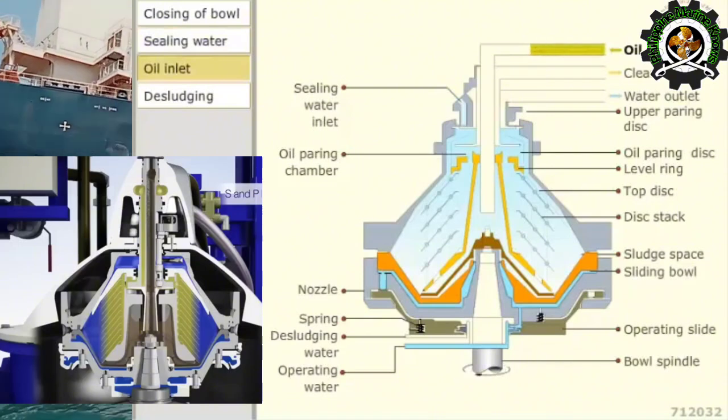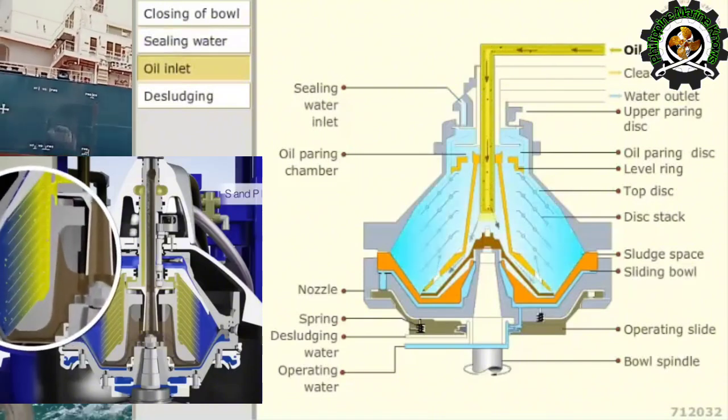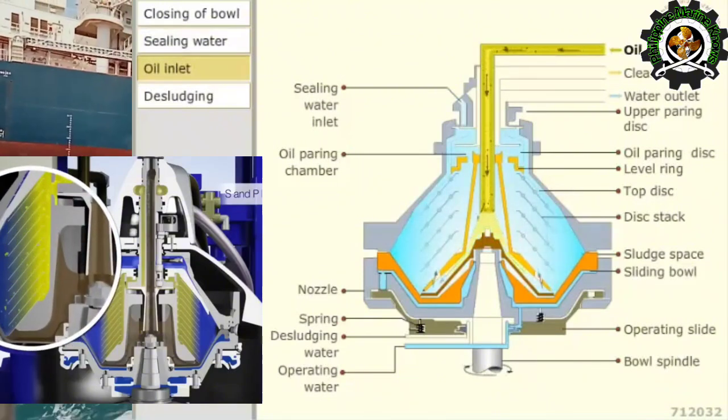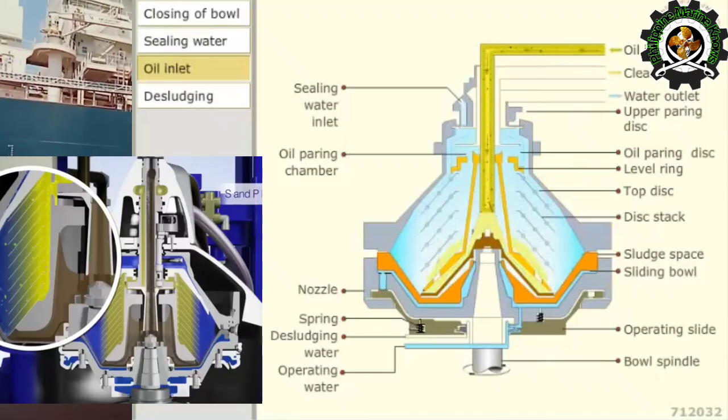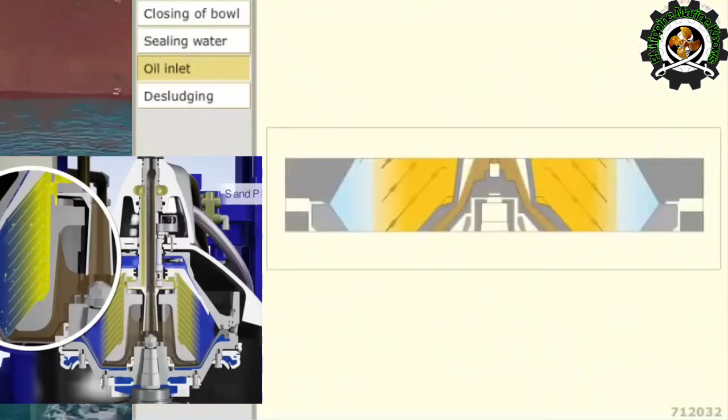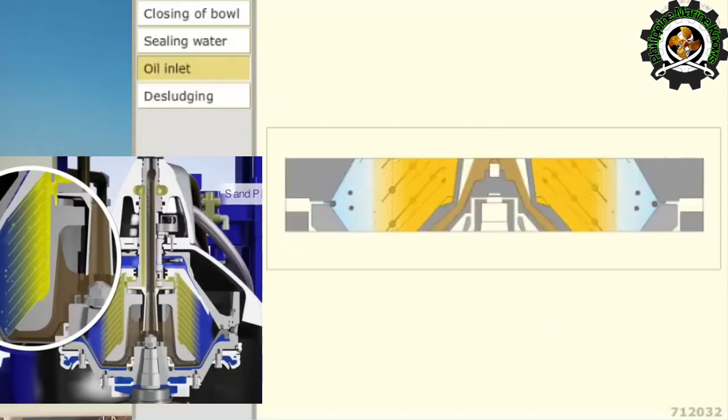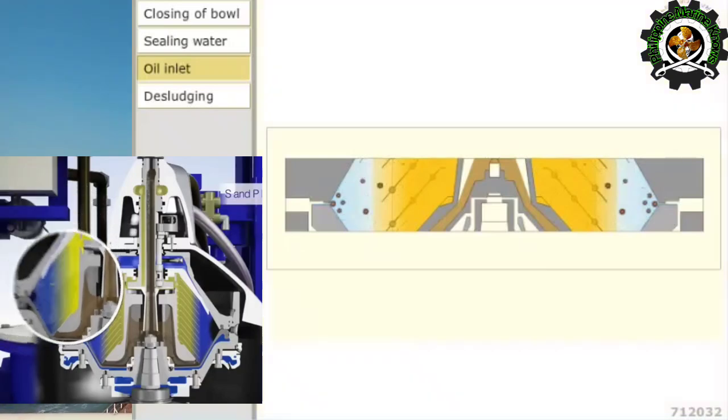The dirty oil is supplied into the bowl to the dirty oil inlet. Due to centrifugal force, the oil displaces the water and the sludge to the bowl periphery and rises upwards through the disc stack.